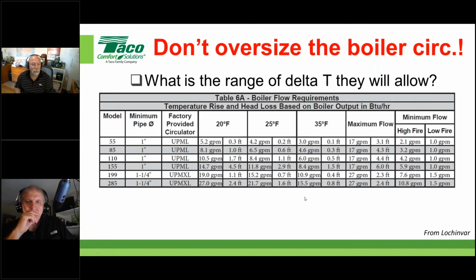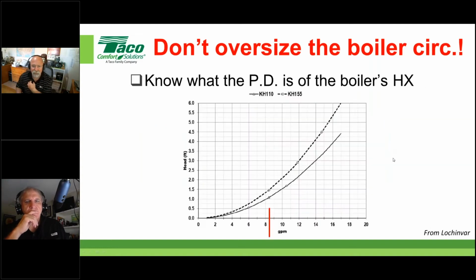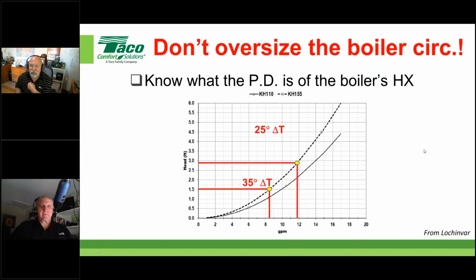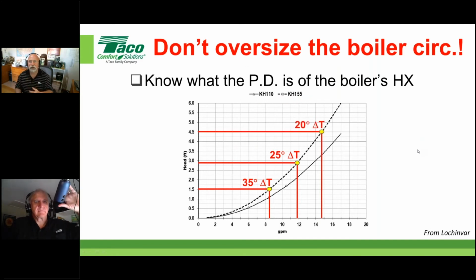Here's one from Lochinvar. Let's go with a 155 for consistency and look at what they're showing you: 20, 25, 35. They even give you a maximum flow and a minimum flow. So look at those as well, if it's given on the same chart or in another area of the manual. But let's do the same thing with this. You go to their chart and see what the pressure drop would be at these given delta T's, again on the boiler side of the situation.